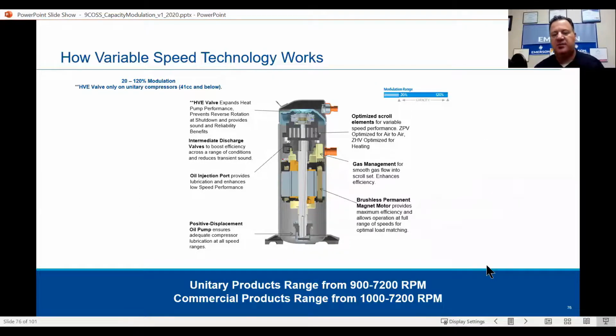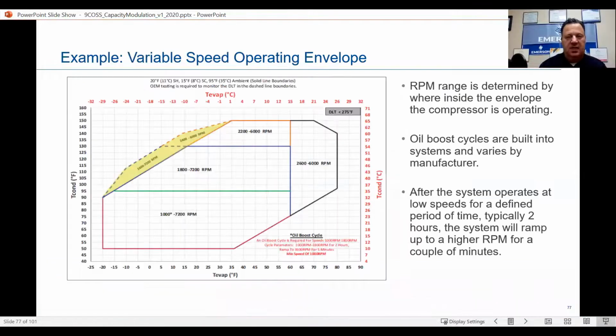Unitary products range from 900 to 7,200 RPMs. And commercial products range from 1,000 to 7,200 RPMs. This is just showing our envelope. Once again, the RPM range is determined by where inside the envelope the compressor is operating. The oil boost cycles are built into the system and vary by manufacturer.